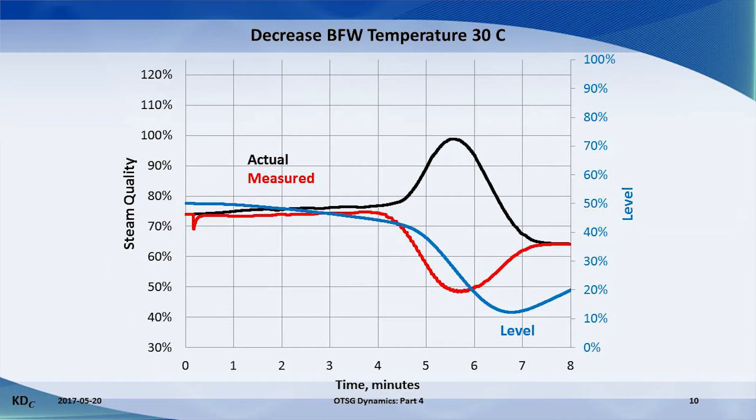This low pressure drop is interpreted as a low steam quality. The level in the separator again tells us what is really happening. The level plummets when the cold front reaches the boiling location and the radiant section starts to boil dry. Then the level gradually rises because the OTSG is delivering more water.